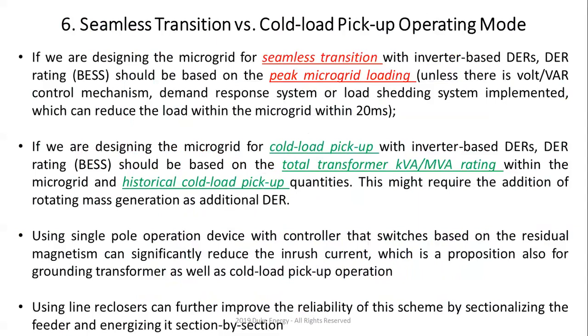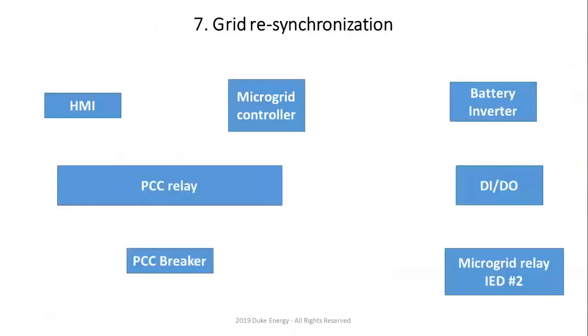So essentially, when you do microgrid for seamless transition, you can do the peak microgrid loading, you can also implement volt-var control if you have it, right? If you do cold load pickup, then you have to size everything for your transformer kVA/MVA rating. And then you have to look at your historical cold load pickup quantities. Unless you start implementing different things on your feeder to sectionalize the feeder and all of your transformers so that you're not picking up everything, you're just picking up sections, et cetera, right? You can also use maybe line reclosers, but that requires you to have some different communication schemes for that stuff, right? So there are a lot of requirements. This is me just telling you basic stuff on the seamless transition versus cold load pickup, right?